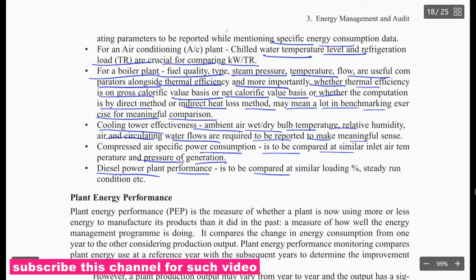Cooling tower effectiveness and ambient air wet and dry bulb temperature, relative humidity, air and circulating water flow are required to be reported to make meaningful sense. Compressed air specific power consumption is to be compared at similar inlet air temperature and pressure of generation. Diesel power plant performance is to be compared at a similar loading and steady state condition.